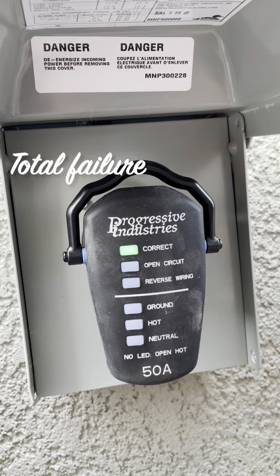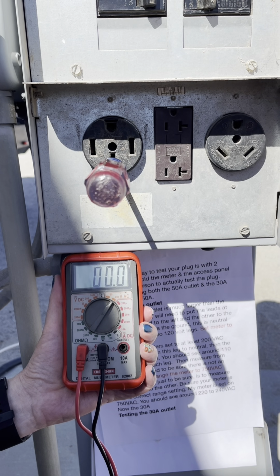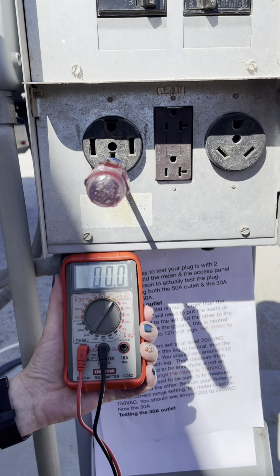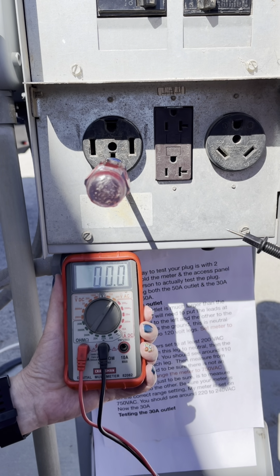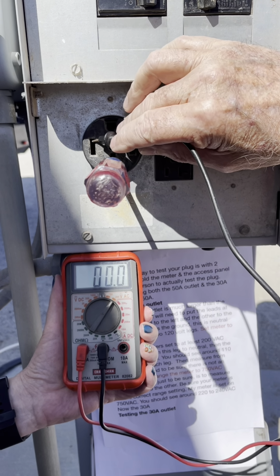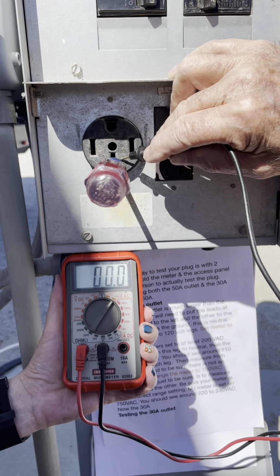The easiest way to test your plug is with 2 people. One to hold the meter and the access panel, and the other person to actually test the plug. I will show testing both the 50 amp outlet and the 30 amp outlet. First, the 50 amp outlet. The inside of this 50 amp outlet is much larger than my meter leads, and in fact, the contact is deeper than my probe will reach. So I'm carefully going to use a flat blade screwdriver to give me access to the contacts. This is a hot leg, this is a hot leg, this is ground, and this is neutral.